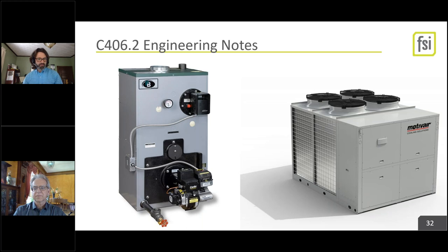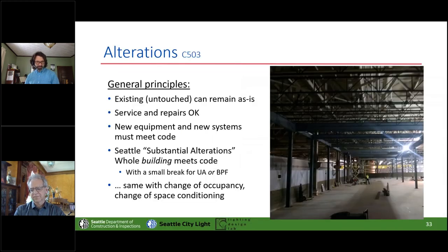Ground source VRF is already very efficient, and the code is already recognizing that. For heat pump and heat recovery chillers, the rating is still getting ironed out with the industry, so being better than that is going to be heavily caveated: it depends, so go discuss it with your code official. And does the higher efficiency equipment cost more? That's one Duane wanted me to touch on. Yes, is the short answer.